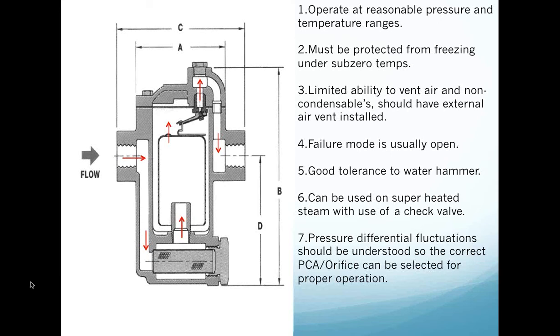This trap is capable of operating at reasonably high pressures and temperatures. It must be protected if you're outside and you're in a colder environment, because if this trap body is processing and then you shut down for a weekend, and I was recently in Montana, and the facility does use inverted bucket steam traps, and they're changing their production schedule, and they're going to shut down over the weekend. In the wintertime, when it gets cold, if that trap body has been processing and then has the ability to go idle during the weekend period, that condensate laying in that body can freeze, and it will break those bodies. So you need to be careful about that if you live in that environment.